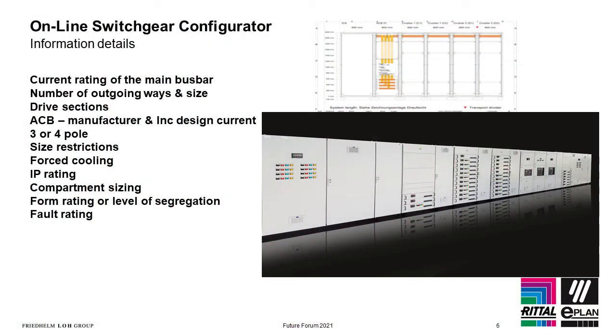Apart from the schematic drawing that you've just seen, other information the software will need is the current rating of the main busbars, of the 3-pole or 4-pole; we do up to 6,300 amps down to 400 amps. That is key information the configurator will need to start the process. Also, the actual size of the compartments. This can be determined by the current rating of the circuit breaker, or the compartment size if it's a motor control centre, for the variable speed drive or transformers, etc. Size restriction is also an important thing.